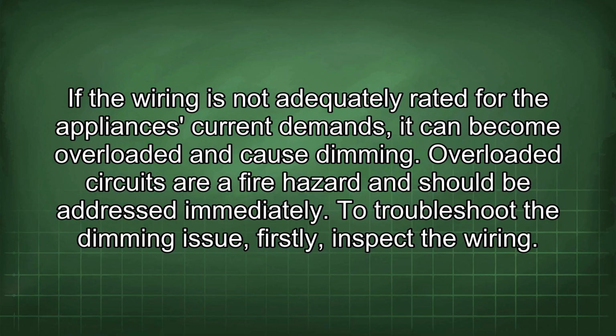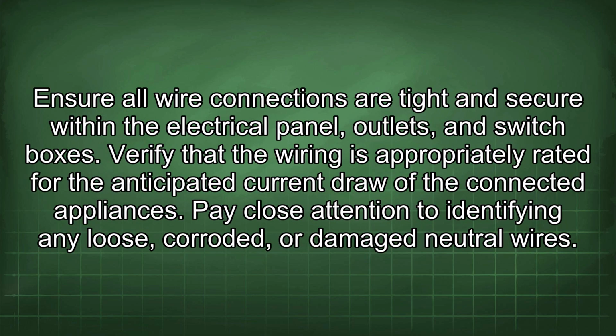To troubleshoot the dimming issue, firstly, inspect the wiring. Ensure all wire connections are tight and secure within the electrical panel, outlets, and switch boxes. Verify that the wiring is appropriately rated for the anticipated current draw of the connected appliances. Pay close attention to identifying any loose, corroded, or damaged neutral wires.